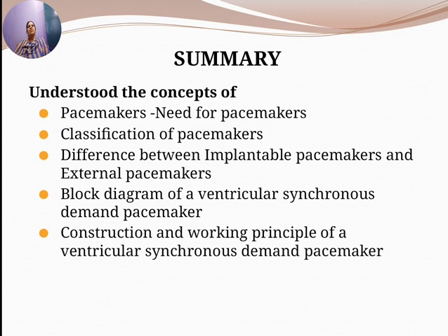There is a special circuit called the voltage monitor circuit which senses the cell depletion and signals the rate slowdown circuit and energy consumption compensation circuit of this event. The rate slowdown circuit shuts off some of the current to the basic timing network to cause the rate to slow down to 80 plus or minus 3 beats per minute when cell depletion has occurred.